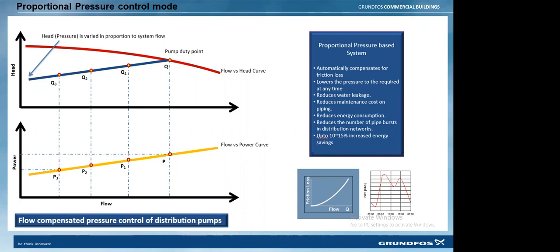So when the flow is varying, at 100% load or 50% load, when there is a reduction in the flow, our friction loss factor components are also reducing. With a better control system, we will be measuring that arithmetic value, and it will be programmed in our controller. We already have the flow reference, and with that flow reference we can calculate the friction losses of your system.